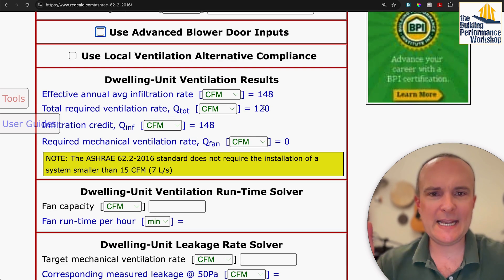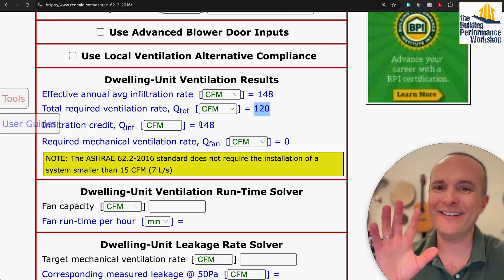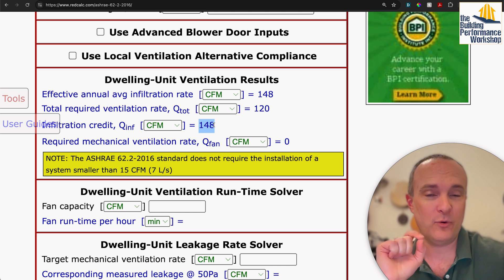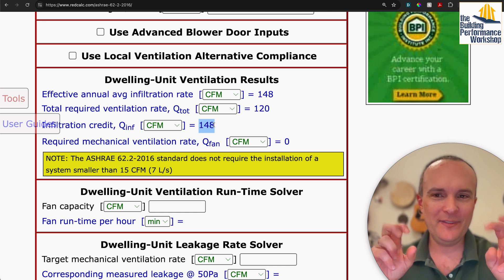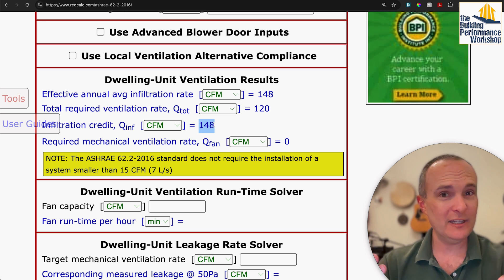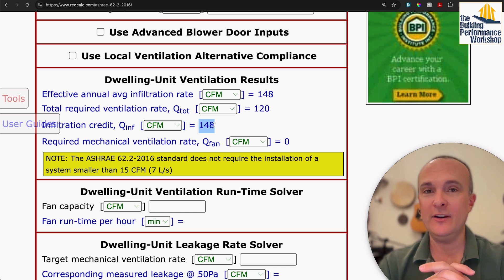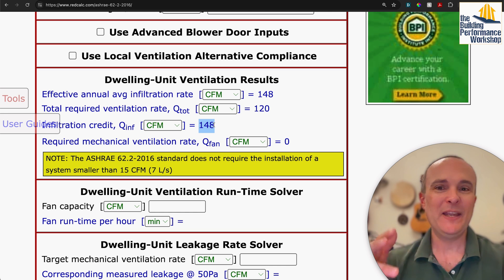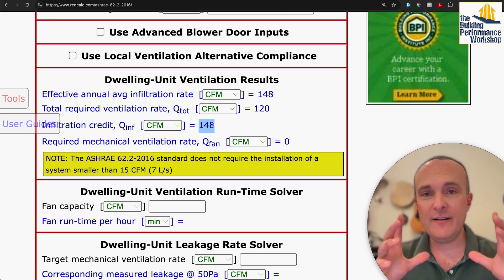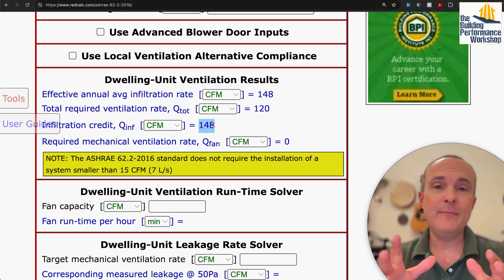The whole house needs 120 CFM of ventilation. The infiltration credit we get from this is 148 CFM — an estimated figure, because actual air leakage into and out of the house is entirely dependent on weather. On a very mild day you'll have very little; on a very extreme day, lots of it. This number is an average of the two. So about 148 cubic feet of air is coming into this imaginary house from outside every minute of every day.